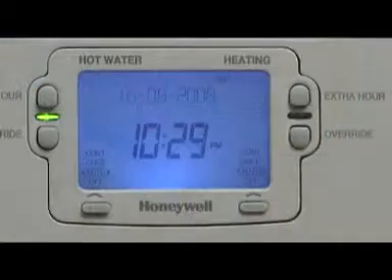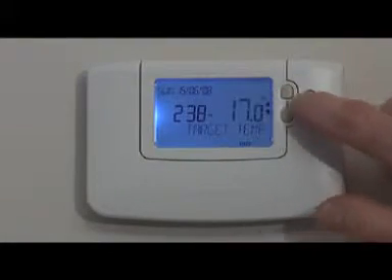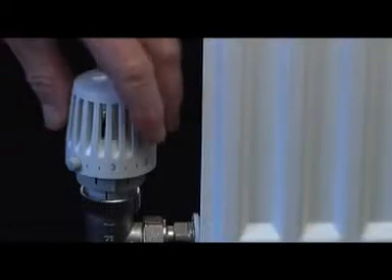The majority of homes do not have a well-controlled heating system — one that switches off when it requires no more heat. To do that, the minimum standard is to have a time control, a temperature control, and a motorised valve hidden in the airing cupboard along with an automatic bypass valve and radiator thermostats.